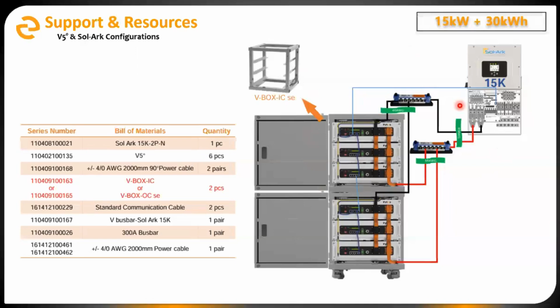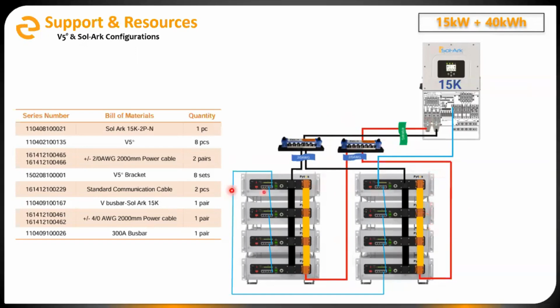Kind of the same thing here, just a slightly different configuration: 2 stacks of 4 batteries, basically 40 kilowatt hours of storage. This is using bus bars as well to combine the 2 battery stacks, but like I said, those could be skipped in favor of the V bus bars or direct cable runs from each stack to the Sol-Ark.